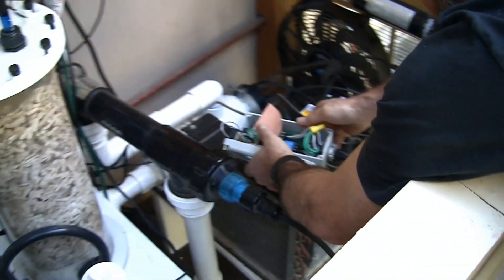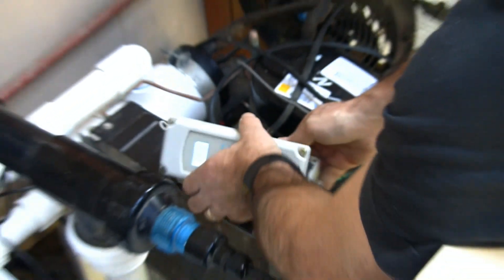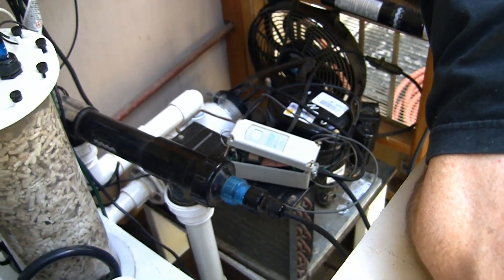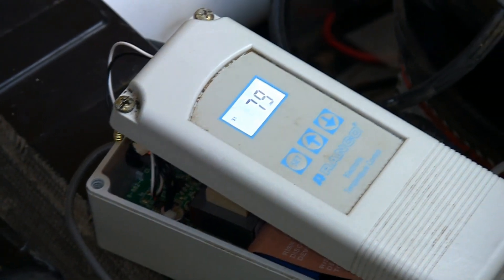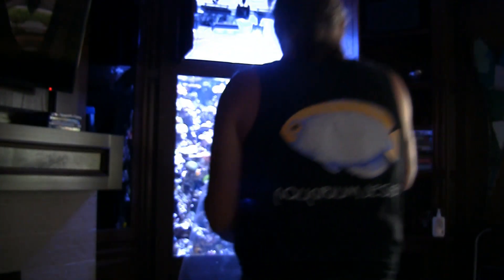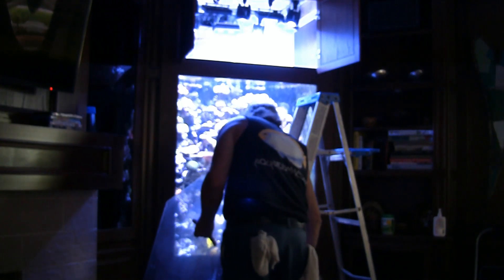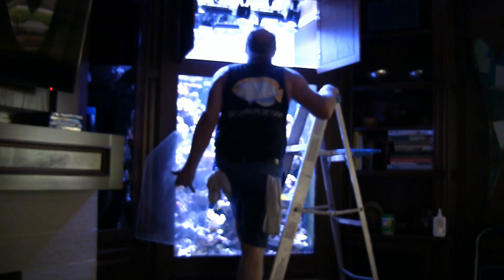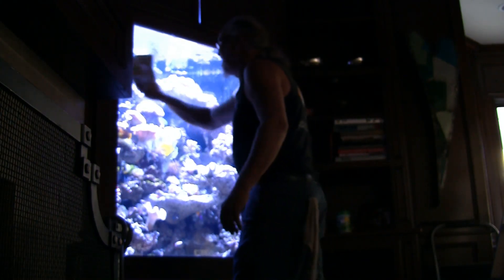What we're working on right now — apparently the digital thermostat for the refrigeration unit has developed a bit of an issue. I think we got water in it when we pulled out the old chiller, so it could be in the process of shorting out. We still have another alternative if that unit ends up having a problem. Once the chiller's re-plumbed and running drip-free, I can reposition the lids back on top of the tank and see if Scott has solved the digital thermostat issue.